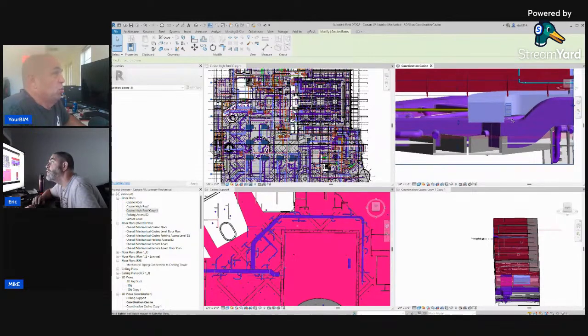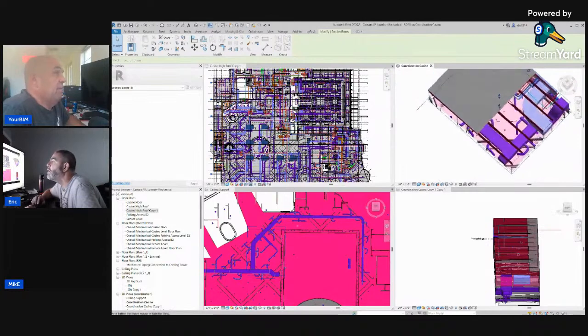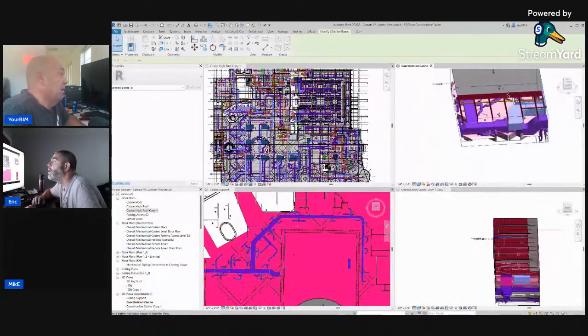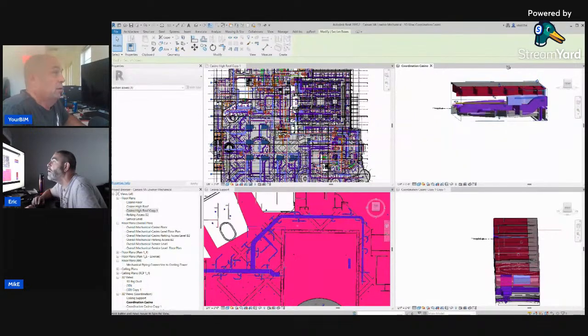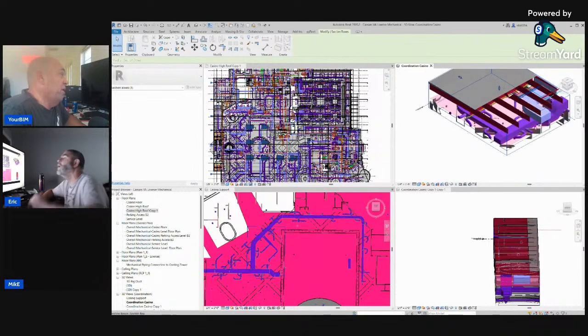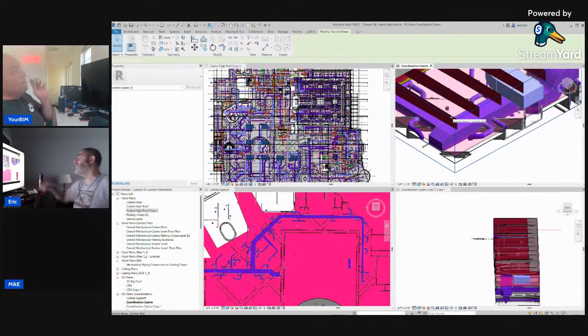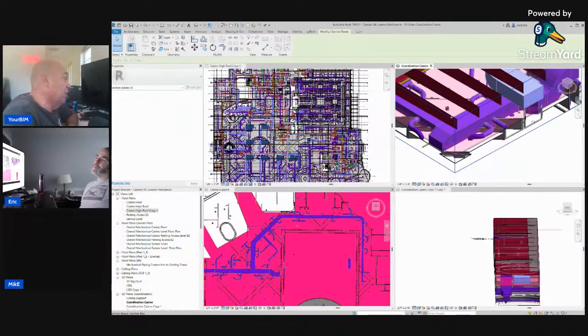You leave that diffuser up there because, listen, here's your problem. You're going to be mad about this. You see that beam that you're worried about it running into when you put it up there? That's because the structural engineers couldn't draw webs in there. Those are all webs. I heard you say that the other day, and I was wondering if you could thread a 24-inch diameter one through those things. I don't know that we want to thread any through the webs because they get real itchy about that. But as far as having an open grill just on this side of the bar joist, it would breathe just fine right through that thing.